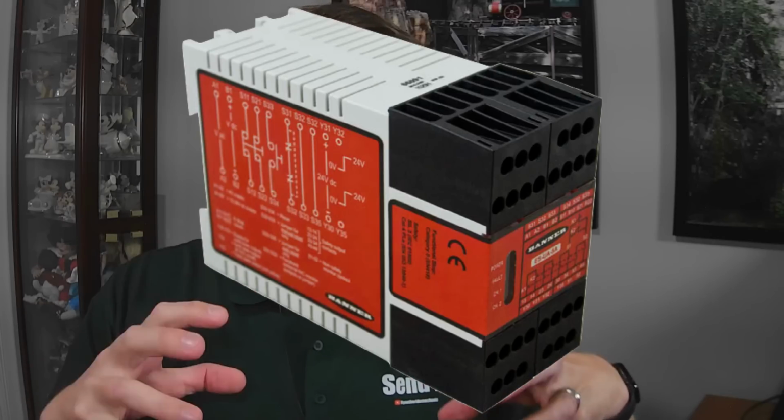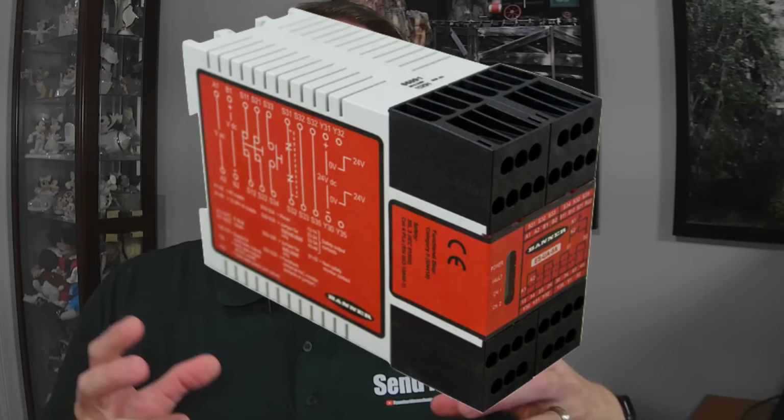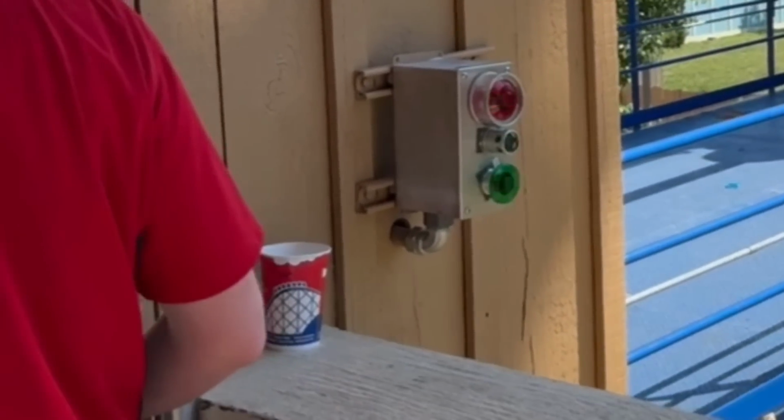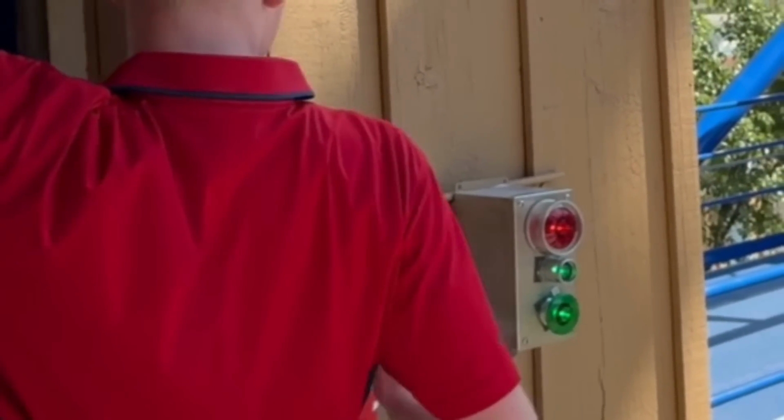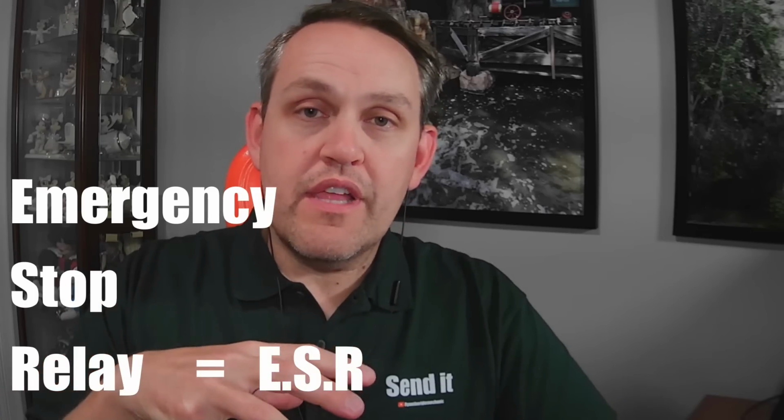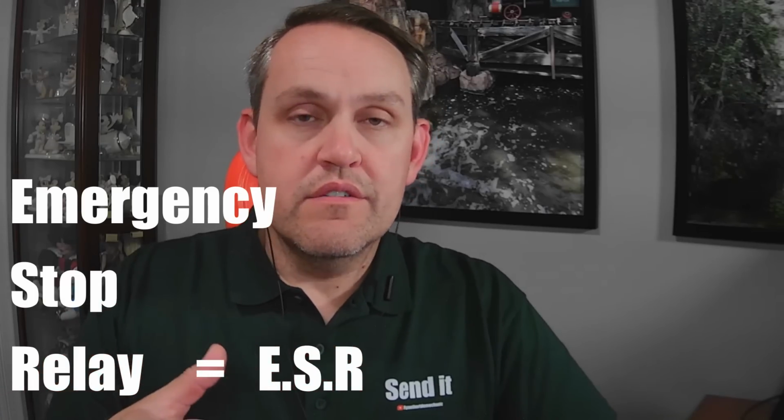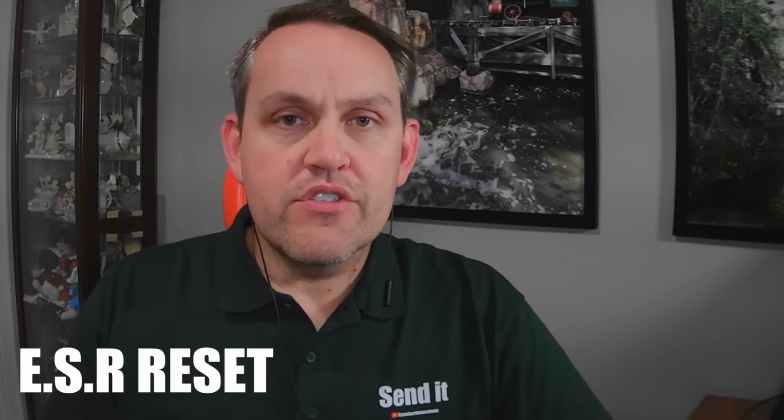And the reason is because those e-stops typically report back to a big relay or multiple relays that are pulled in. So those relays are out, they're not activated. So when you pull those e-stops out, that thing in the middle, that big relay, is not active. It's not ready to go yet. So the PLC needs to send a signal to that relay to pull it in the first time. And then once it's pulled in, the power from the e-stops keeps that relay electrically latched, so it's ready to go in the future. So that is called an e-stop relay. So you have to reset the e-stop relay, or ESR for short.